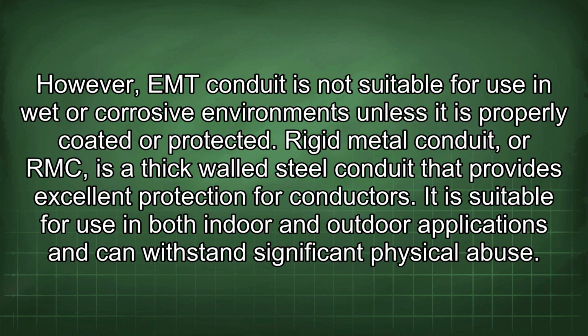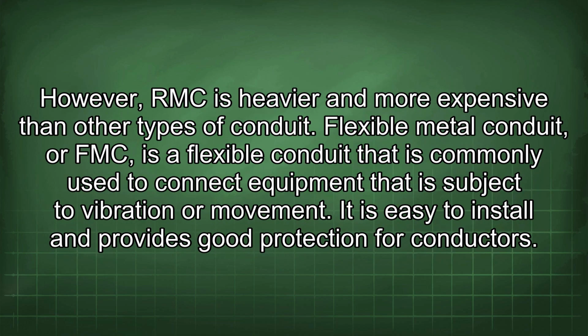However, EMT conduit is not suitable for use in wet or corrosive environments unless it is properly coated or protected. Rigid metal conduit, or RMC, is a thick-walled steel conduit that provides excellent protection for conductors. It is suitable for use in both indoor and outdoor applications and can withstand significant physical abuse. However, RMC is heavier and more expensive than other types of conduit.